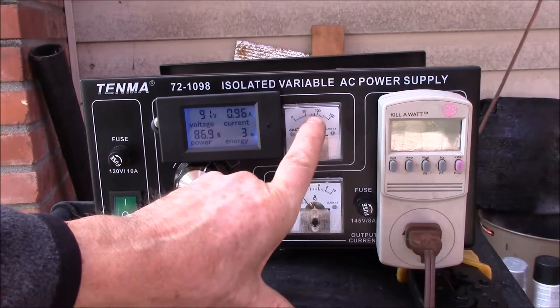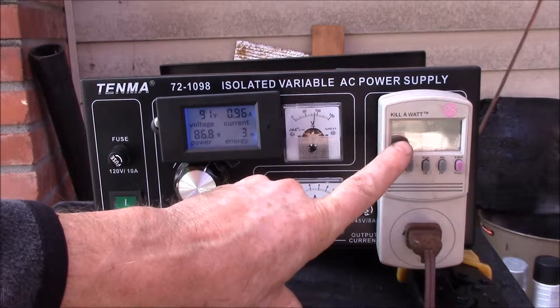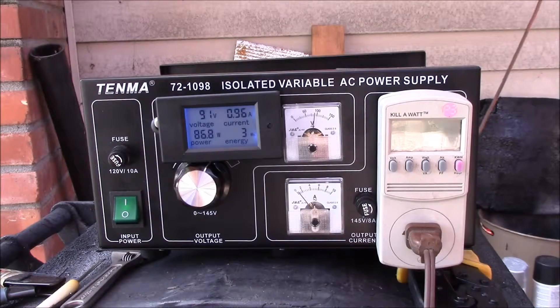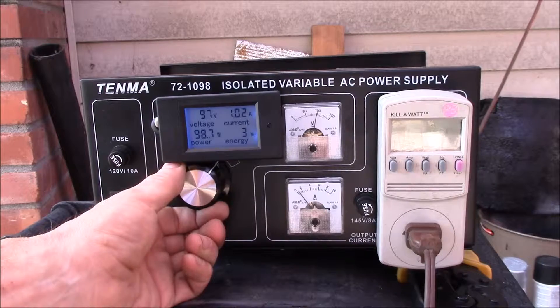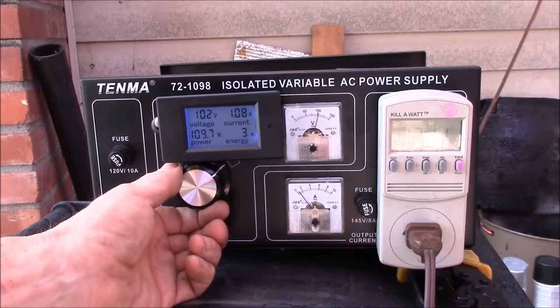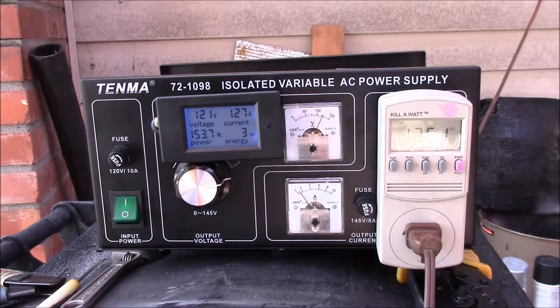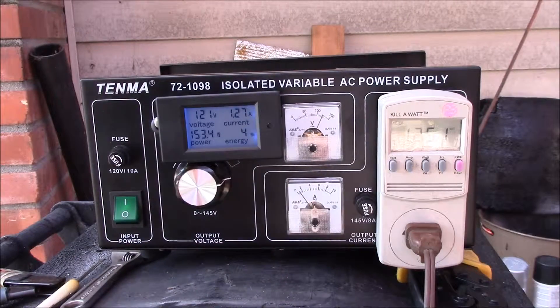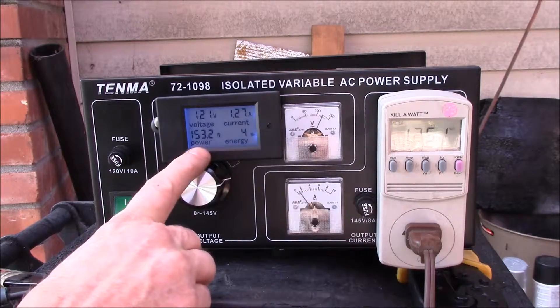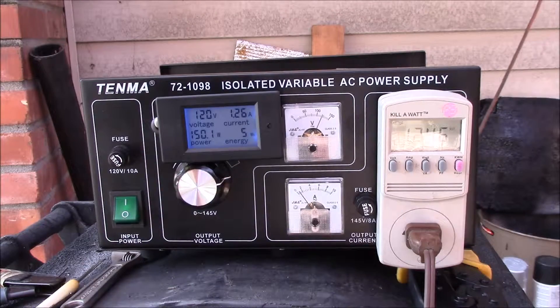At 9.1 volts, that kilowatt meter is just barely reading, and this one says 120 volts - so the voltage on this meter is off. You can see as the voltage comes up the display gets a little better. Going up to 120 volts, it's reading 125, and with a 150-watt infrared heating lamp in there it's reading 153 watts. But if I go to 120, look at that - 150 watts.